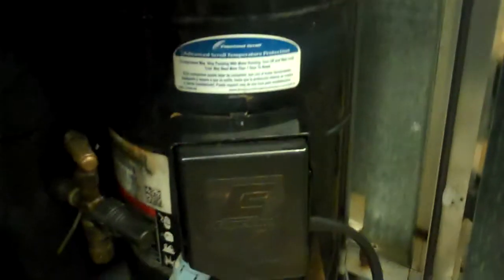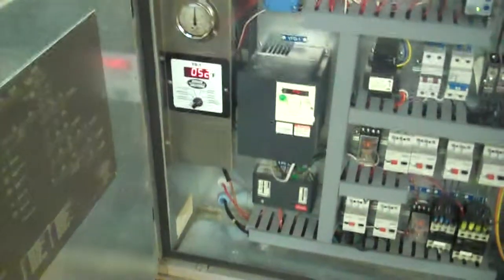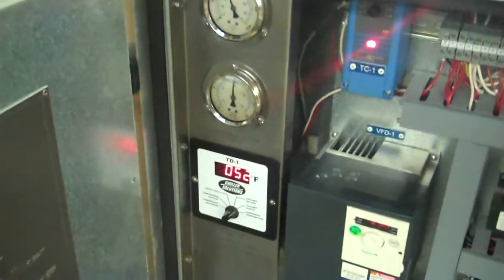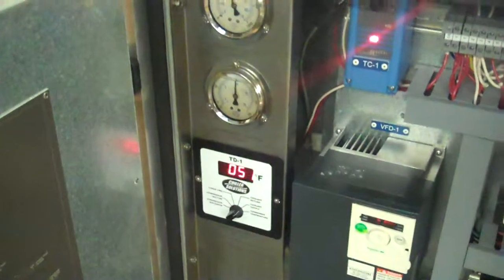The compressor overall is pretty quiet for something of this size. Again, the units are nicely engineered. You have a hard printout of the schematic and the piping schematic. Here's the piping schematic on this door, and here's the electrical schematic on this door here. We're able to run it without the cover just for this test to show you everything. That's the other cover right there. And of course, on this side we have the cover too. So we're going to come back in a minute for video number 2, just to show you it cycling on and off at about 20 or 22 F range.